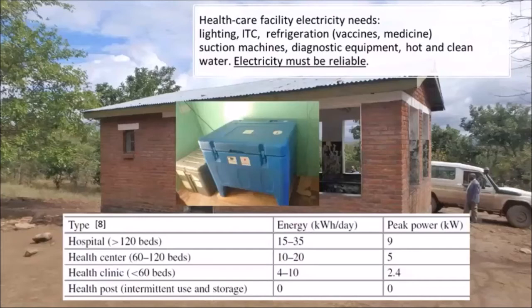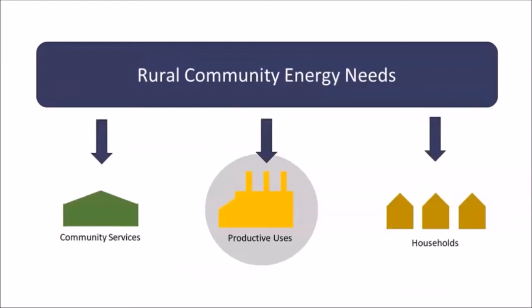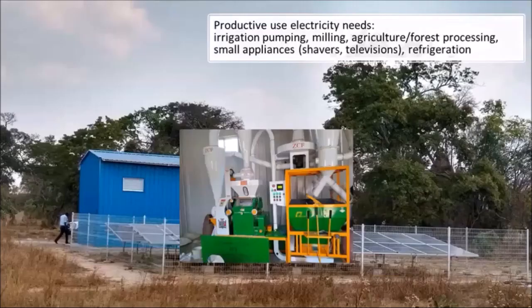Healthcare facilities have the same lighting and ITC needs, and their lighting needs are perhaps more pressing in case of emergencies in the middle of the night. But they also need electricity to run diagnostic equipment and various machines for healthcare. One important application is refrigeration for vaccines and medicines — there's a picture here of a solar-powered vaccine refrigerator. It's very important to keep vaccines and medicines within a very narrow band of temperatures. So if your organization is seeking to provide electricity to a health clinic, you have to make sure it is reliable. There's also a table of typical energy use and peak power needs of healthcare facilities, which are important inputs for any design.